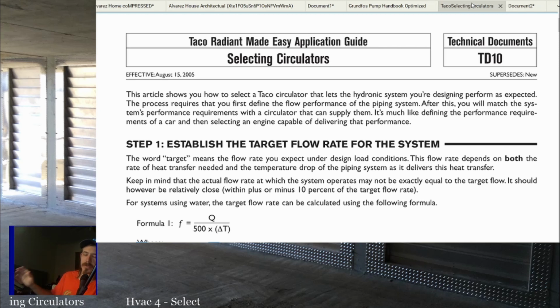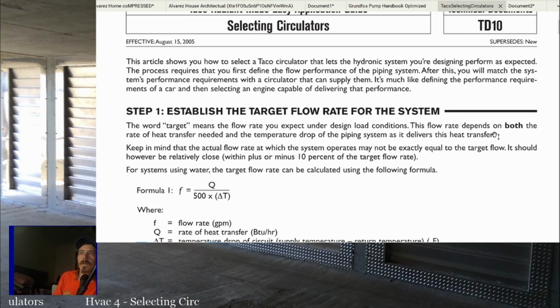The feet of head is how much friction it has to overcome in the piping. Now, like I said, in those other pumps, the friction in the piping still matters, but it's usually going to be minimal compared to the amount of head pressure it has to be able to pump. So again, that condensate pump that can pump 18 feet of head can basically handle creating about 8 psi. You know what I mean? That pump can create about 8 pounds of pressure, and that's it. So it can't pump any higher than 18 feet because it can only create 8 pounds of pressure. But when we talk about circulators, we got to talk about overcoming the piping.